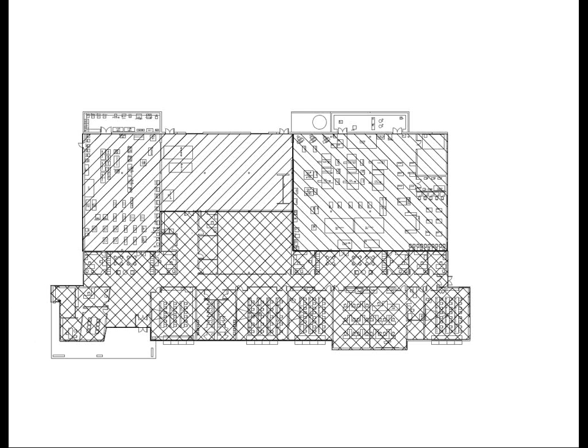So how do I model that heat pump chiller? I've never done an eQUEST model before, didn't know what it was. So I started looking around and looking through the eQUEST help documents, and lo and behold, they do have an option. It's not available in the wizard, but once you get into the detailed interface, there's this heat pump chiller, a loop-to-loop heat pump chiller, which cools a chilled water circulation loop and simultaneously heats a hot water loop. So I thought, great, easy.